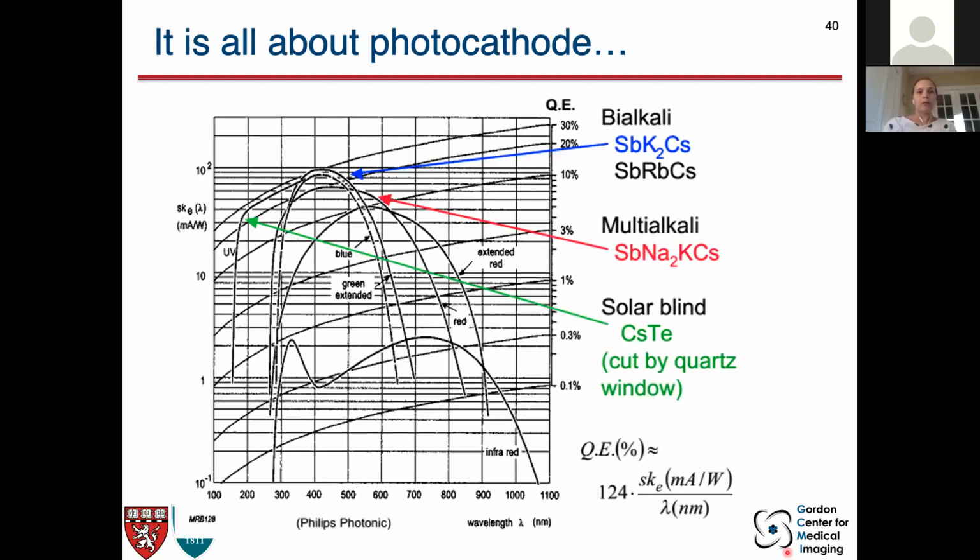And for a photomultiplier tube, the photocathode material is very important. This quite messy slide shows the quantum efficiency as a function of wavelength for some different photocathode materials. The take-home message here is mainly that different photocathode materials are sensitive to different wavelengths. We see that these spectra all peak around a certain wavelength. So for an efficient detector, we want to match this spectrum with the emission spectrum that we saw for the scintillator itself.